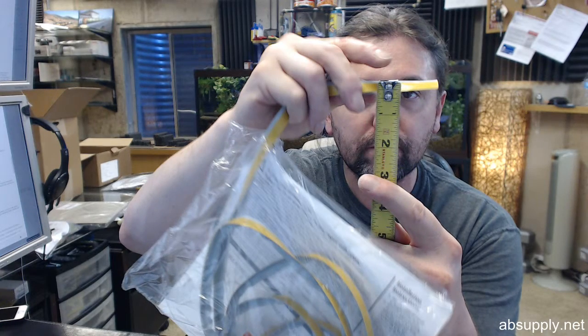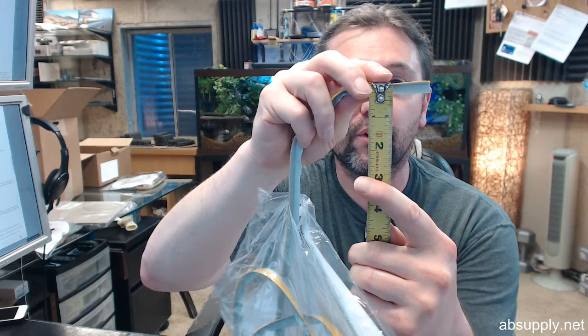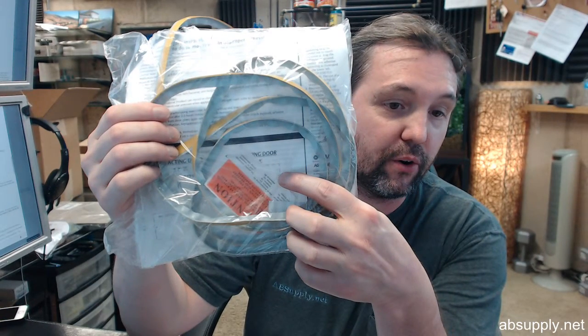There's an image below this video showing the important dimensional properties of this item. You can see that the width of the backer is 7/16 and that the projection is 9/32, so just heavy on a 1/4 inch. Now, where you're going to use this, again, is in those pairs of doors that require a smoke seal, a draft seal sort of rating, meaning there's an actual label that is required, and this material even includes that label for application to the frame to testify the material installed meets the criteria and the requirement.